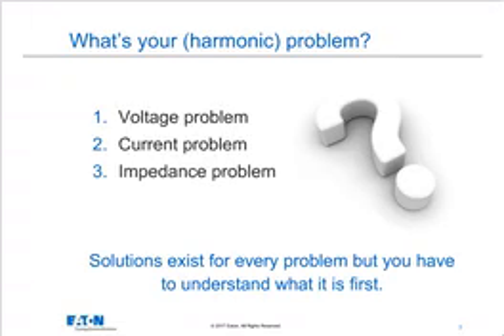So once you look at harmonics, again, harmonics are not a problem unless they're a problem. Well, what is your harmonic problem? Is it a voltage problem? Do I have misoperation of equipment? Is it a current problem? Do I have heating of equipment? Is it an impedance problem? Do I need to change out some of the components of my system? There's solutions for every problem, but first you have to understand what the problem is.